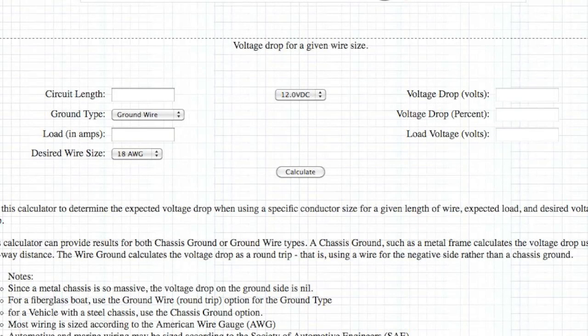This is a clear example of the operational problems you're going to run into in a DC wiring environment, where an excessive voltage drop occurs long before achieving the maximum current capacity of the wire. Now we're going to look at the calculator again. However, now we're going to use the second calculator, which will provide some indication of what will happen if we increase the load on the wire.